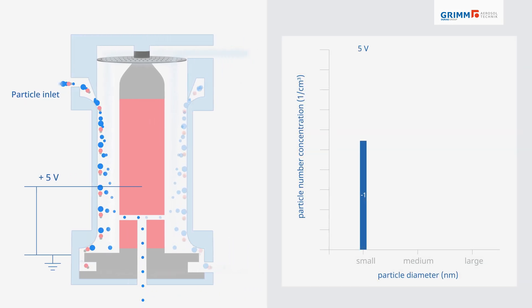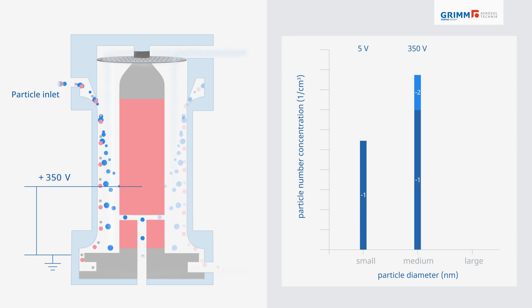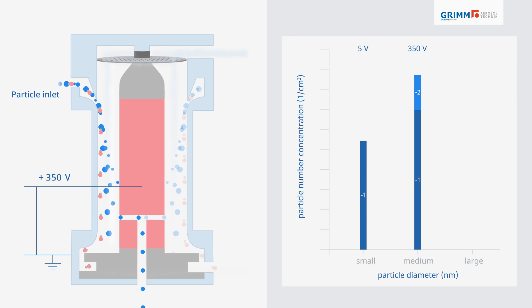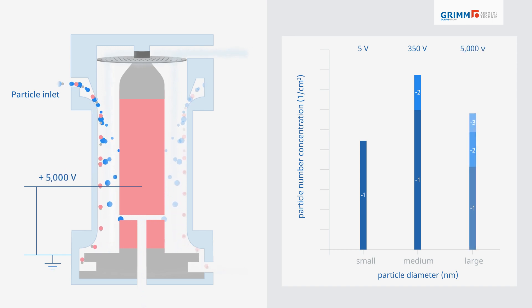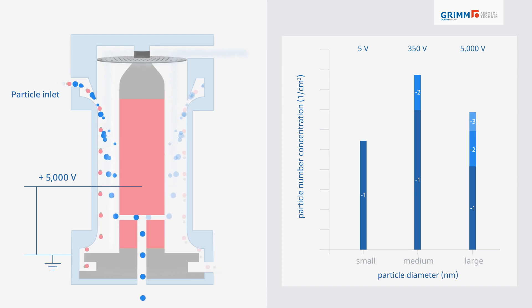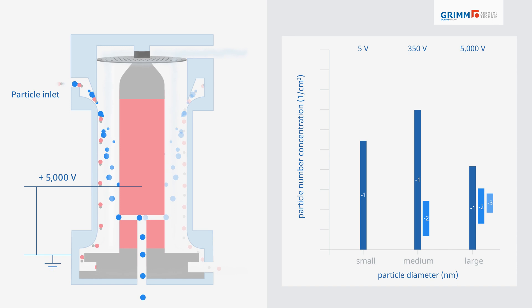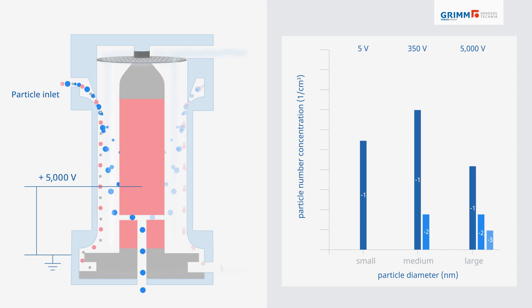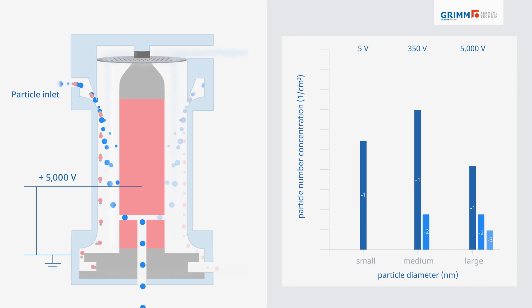This graph shows the correlation between applied voltage and particle size derived from differing electrical mobilities. Larger particles may be multiply charged, and this increased electrical mobility causes them to act like smaller particles. A multiple charge correction must be applied to sort particles into the correct size bins.